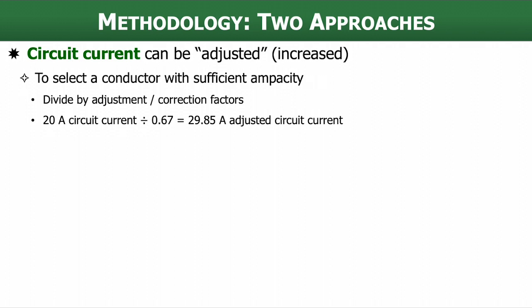For example — and we'll talk about these throughout the presentation — we divide by the adjustment or correction factors we apply for temperature or numbers of conductors in conduit. If we have a circuit current of 20 amps and correction factors that are less than one — decimal values — we divide: 20 amps divided by 0.67 gives an adjusted circuit current of 29.85 amps. We need a conductor rated for 29.85 amps. Essentially, because of the conditions the wire will operate in, it needs to be able to carry more than the actual circuit current, and the correction factors tell us how much more.